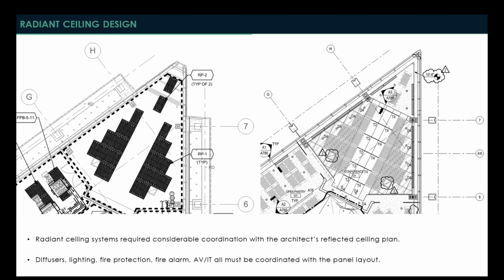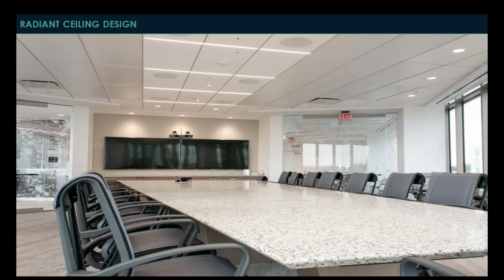When you're taking 50 to 70% of the ceiling and making it active radiant ceiling panel, that doesn't leave a whole lot of space left for lights, fire protection, fire alarm, AV/IT equipment. All these things need to be coordinated. So the image on the left is a mechanical drawing. The image on the right is an architect's RCP. And the end result of that is this space. So this is the actual space that those two drawings were showing.